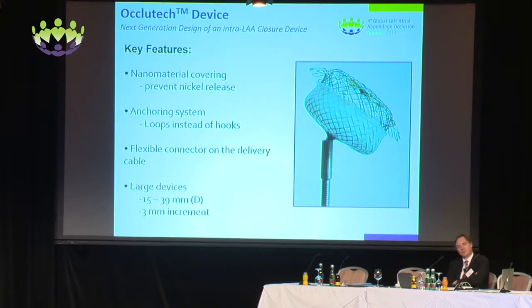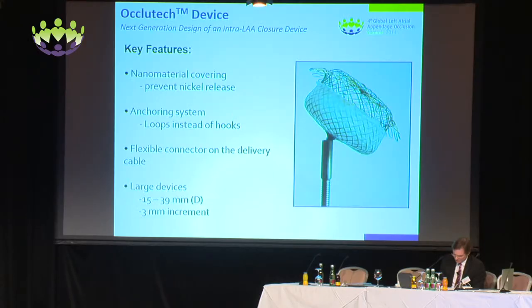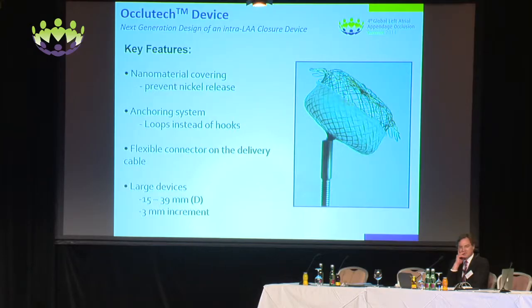Another device that will come, and there's no human implant of this device that I know of so far, is the Occlutech. It's pretty much an Amplatzer, but covered with nanomaterial to prevent nickel release. The anchoring system is made with loops instead of hooks to prevent potential perforation in the appendage. There's a flexible connector on the delivery cable to assess the position of the device in the appendage before release. And there's a large range of devices, up to 39 millimeters, so very large, with a 3 millimeter increment from 15 millimeters, so a wide range of devices to treat many different appendage sizes.